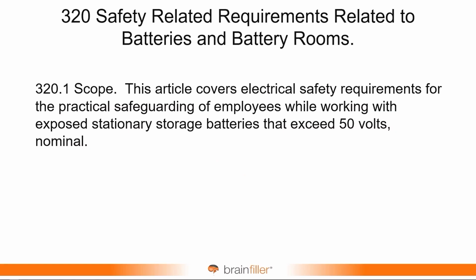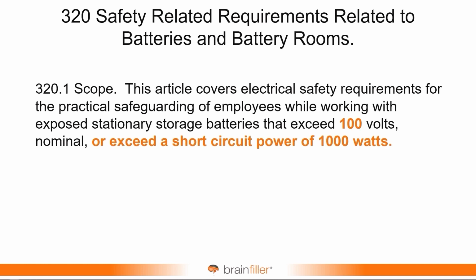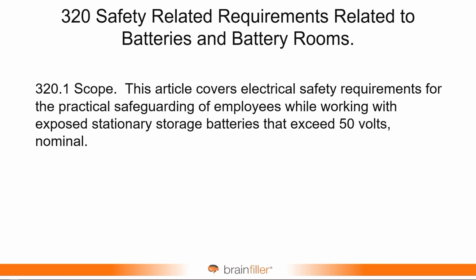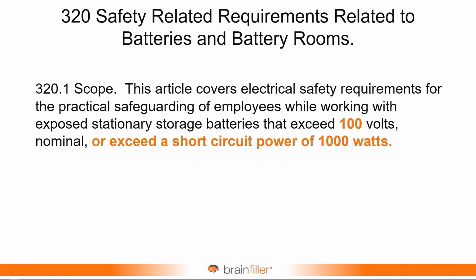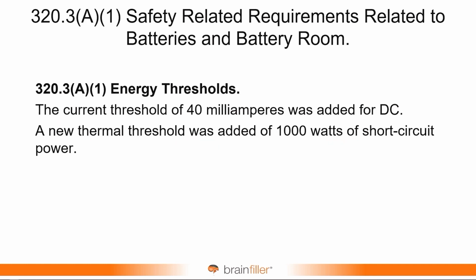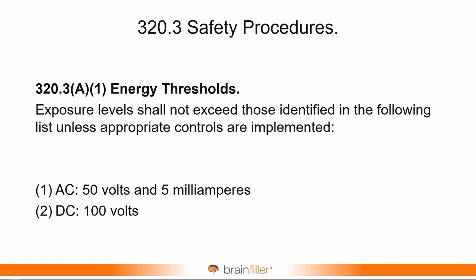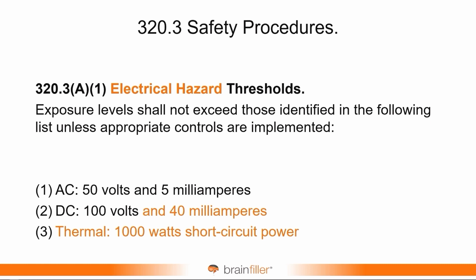Article 320, there was a modification to the scope. And the modification was storage batteries that exceed 100 volts or exceed a short circuit power of 1,000 watts that could cause burn injury. It was 50 volts. It is now 100 volts. Why? Well, there's a couple reasons for that. The energy thresholds were also modified. What we have now is the energy thresholds, DC 100 volts and 40 milliamps, and then the thermal hazard, 1,000 watts of short circuit power.